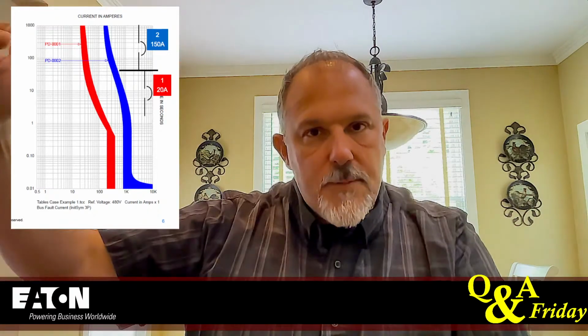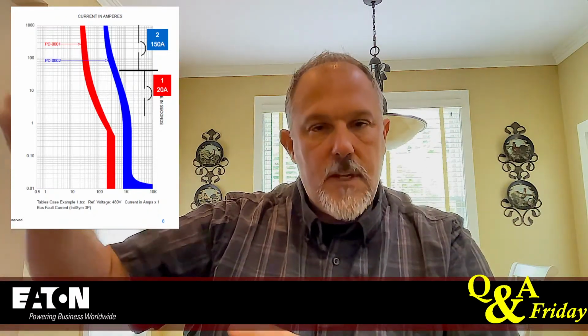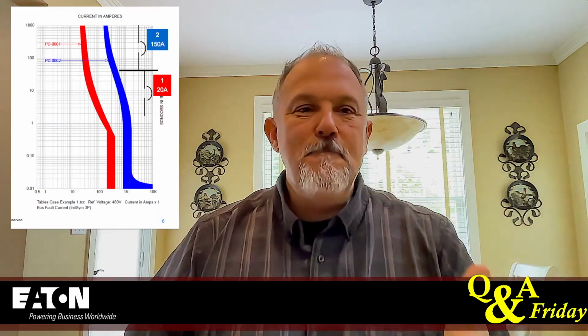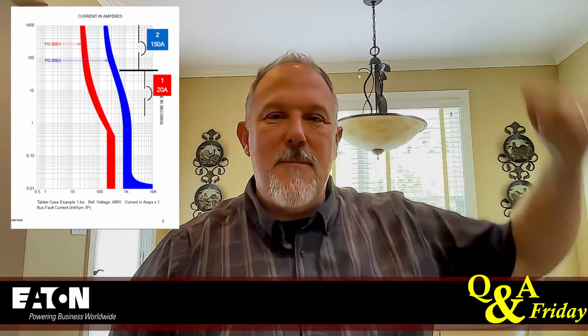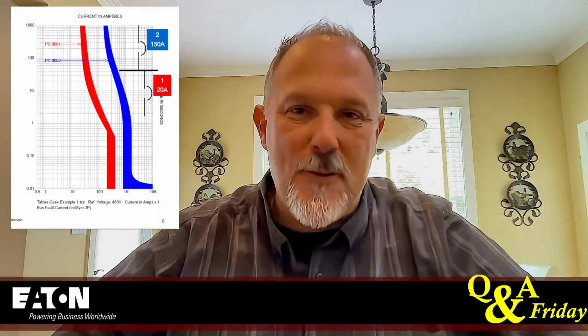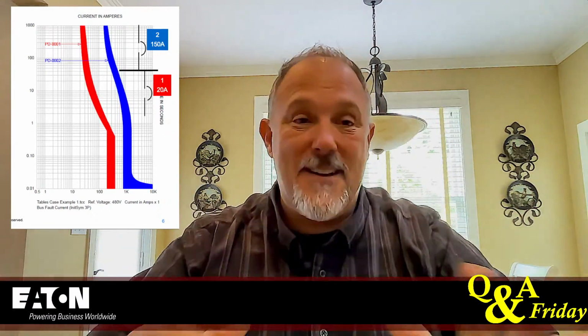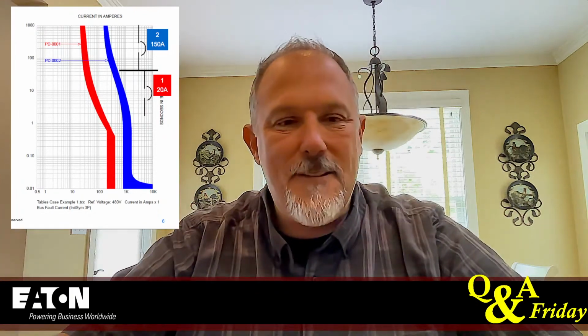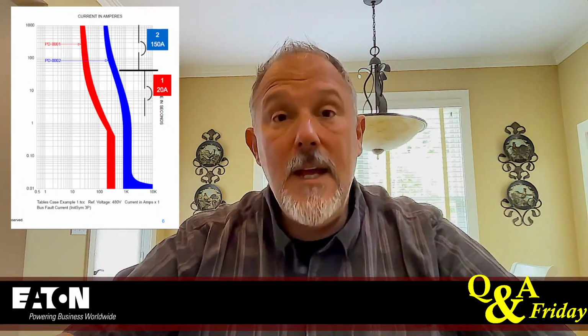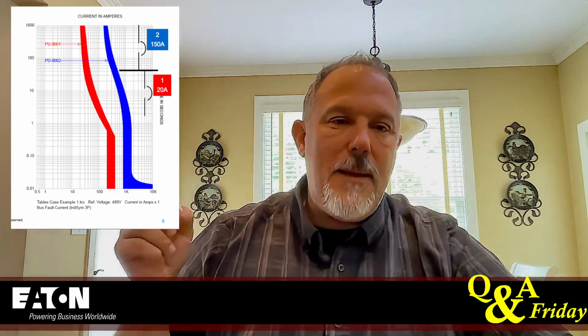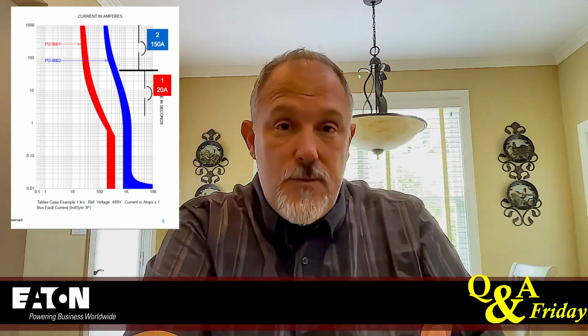So I can increase the upstream overcurrent device's size, and I can still use the tables, or I can reduce the fault current by putting a transformer in, or tell your electrician to take a few laps around the block with his conductor, right? Go down 4 floors, come up 7 floors, and come back down 3 floors, and you're golden. You just added a ton of copper, and you can reduce the fault currents. And then your third option is that BAB20, that's downstream, the red curve. You can take that and replace it with a fuse.